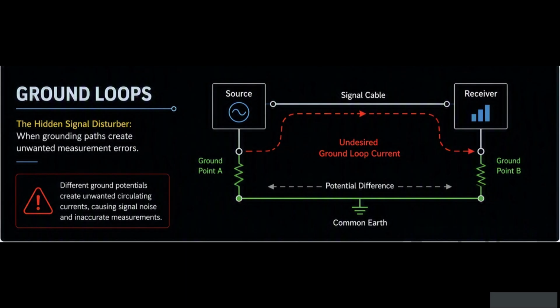In industrial plants, where sensors and control systems may be located far from the control room, ground loops can become a significant source of measurement errors. Even small voltage differences can introduce noise into low-level instrument signals. This is one reason why proper grounding and shielding practices are so important. Engineers must ensure that signal grounding is carefully designed to minimize the possibility of ground loops and maintain signal accuracy.